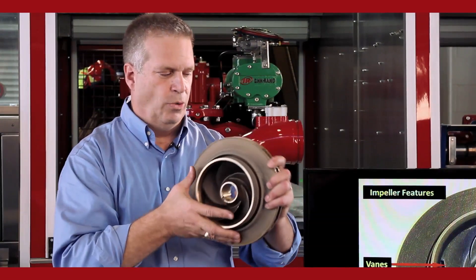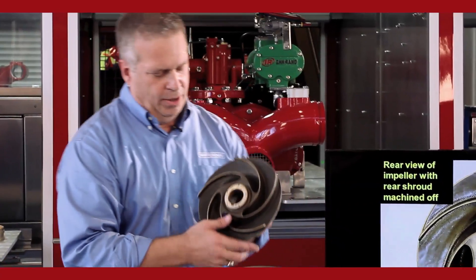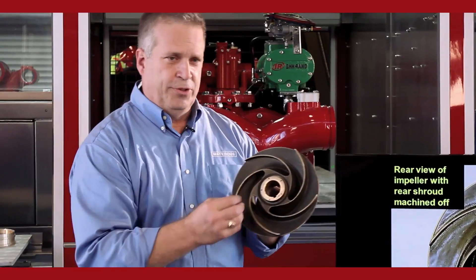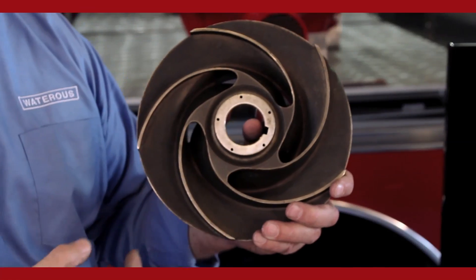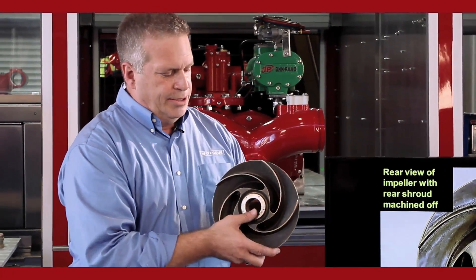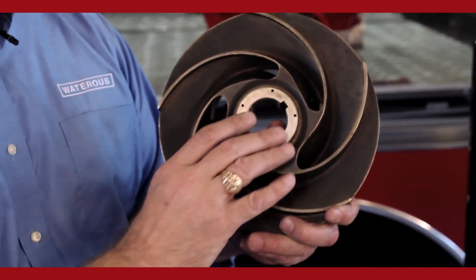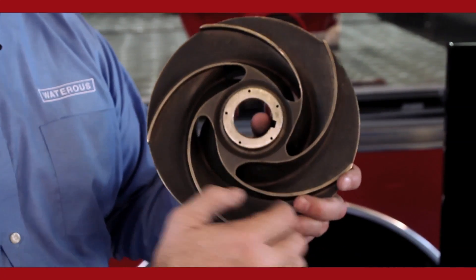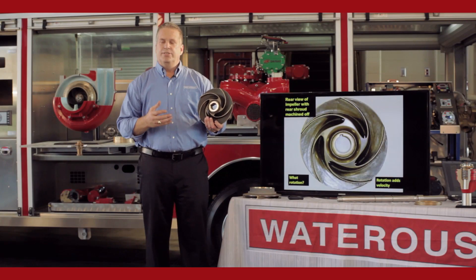Now we cut away the backside of this impeller so you can see how the impeller actually functions. The vanes of the impeller start off in the eye of the impeller. Centrifugal actually means the force starts in the middle and makes its way towards the exit way. What an impeller actually does is add velocity to the water — speeds it up, makes it move faster. As this impeller rotates, this side of the vane will hurl the water out of the impeller and send it out towards the exit way, out into the pump body to the discharge side of the pump. What an impeller is doing is adding velocity, speeding the water up.